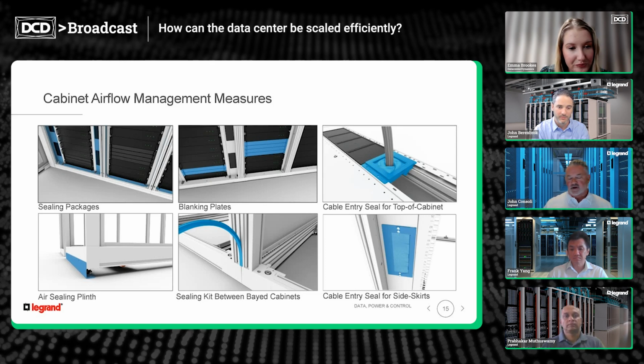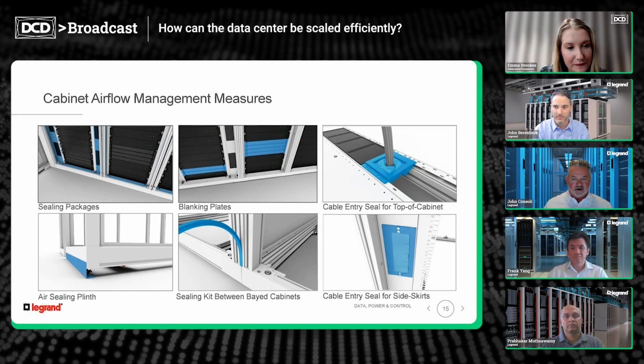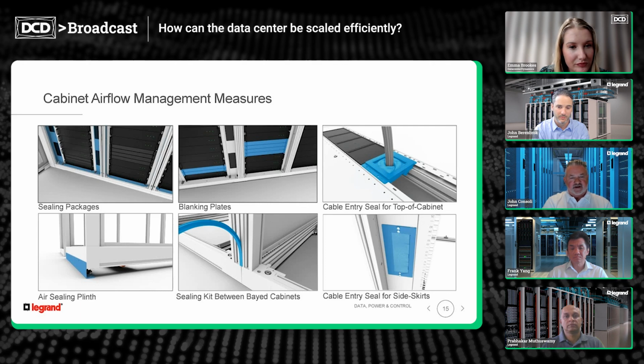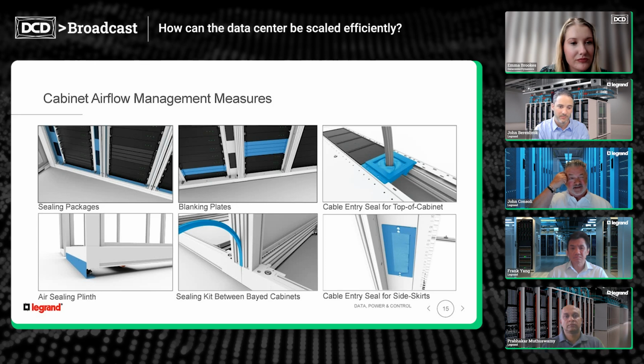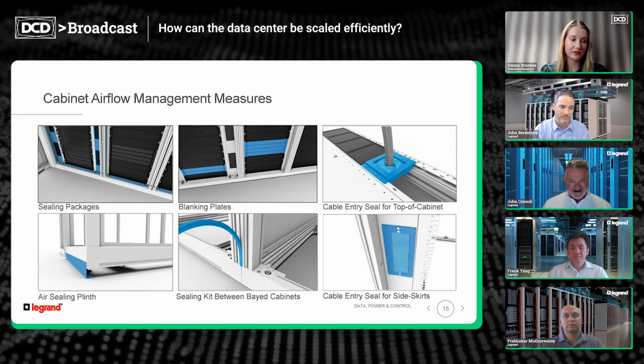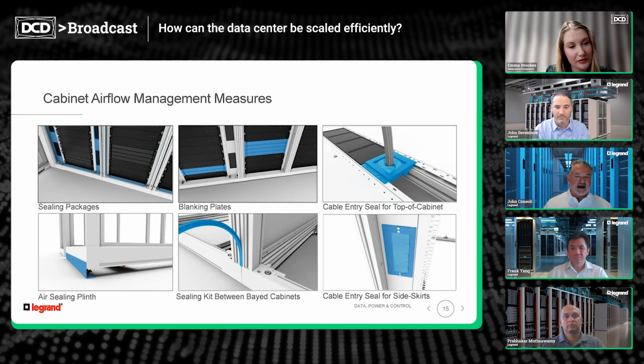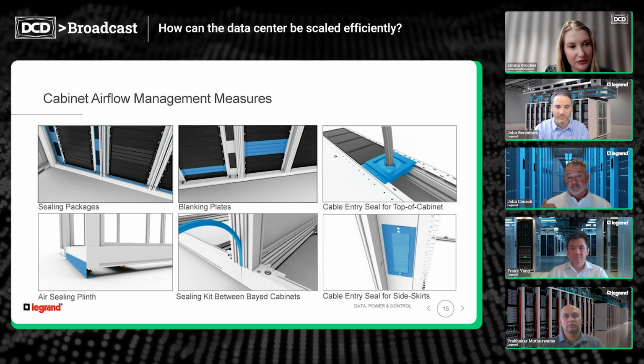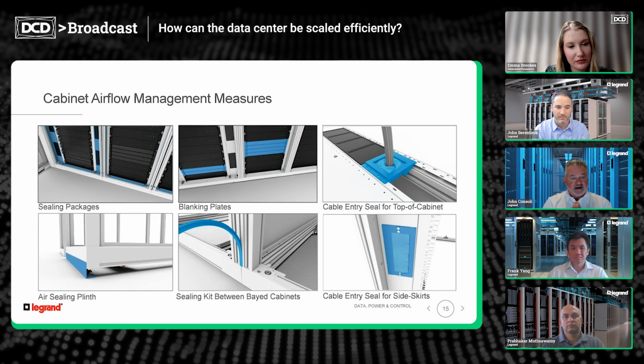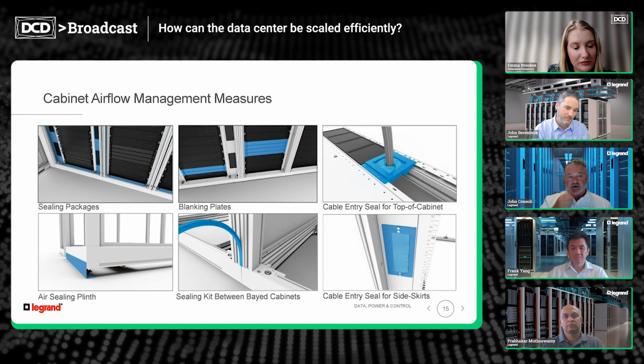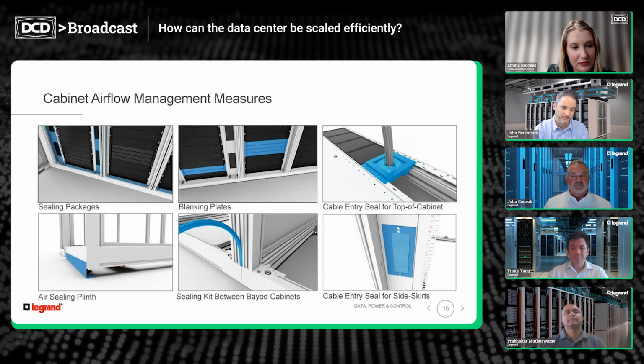We make available, and so do others, sealing packages that are commercially available from any cabinet manufacturer—not just blanking panels and empty spaces. The racks are being populated now, so there aren't many empty spaces in the mounting area, but any place with cable access or egress, use cable seals and brushes. Sealing between bayed cabinets is extremely important. As you see bottom left, we've got air sealing plinths for airflow that might move underneath the cabinet. We just need to be diligent, because it costs a lot of money.